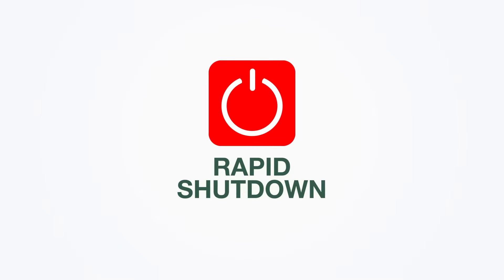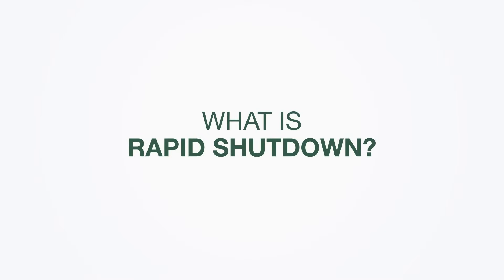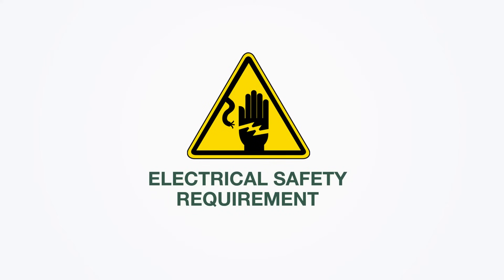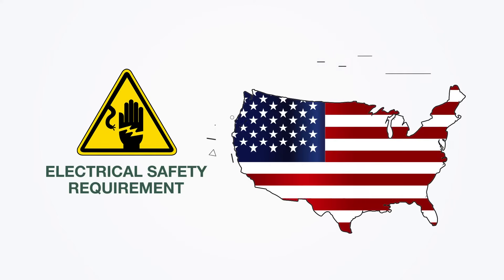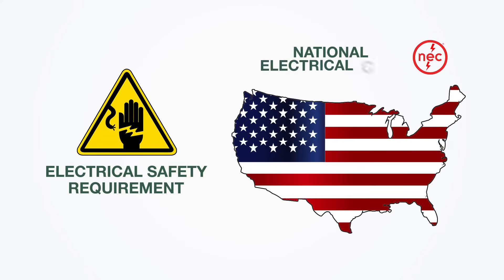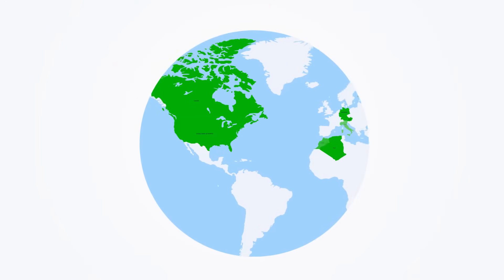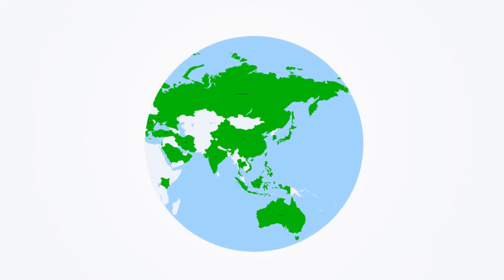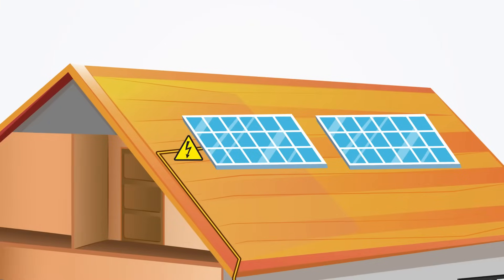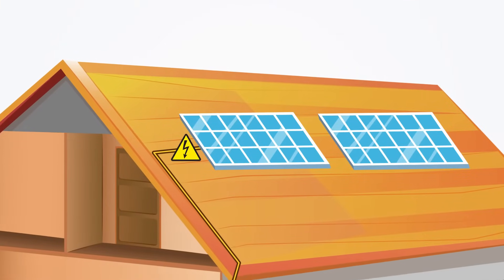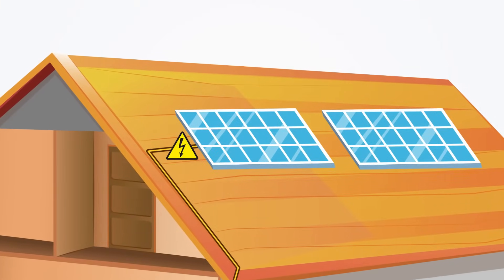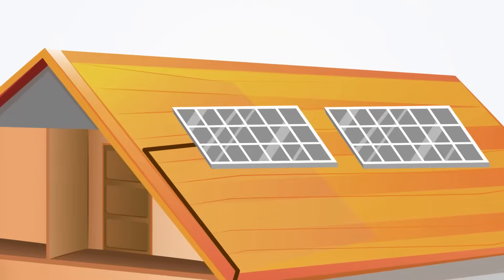That's where rapid shutdown comes into play. So, what is rapid shutdown? Rapid shutdown is an electrical safety requirement that was originally introduced in the United States as part of the National Electrical Code. And now, similar requirements are being implemented all around the world. This requirement applies to new solar installations and requires a way to de-energize rooftop solar arrays by adding an on or off switch.